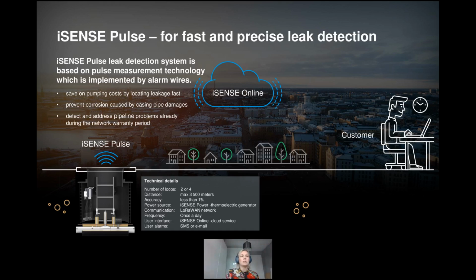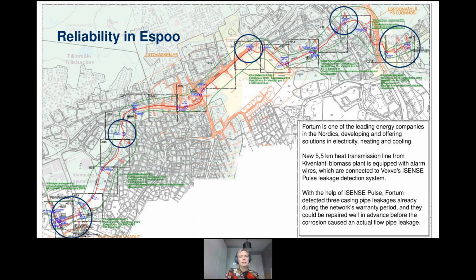And with the leak detection system, you can save on pumping costs by locating the leakage fast. You can prevent corrosion caused by casing pipe damages, and you can detect and address pipeline problems already during the network warranty period, like in the sample case I will show you from the Fortum network in Finland. This is the case example at the Fortum network in Finland.